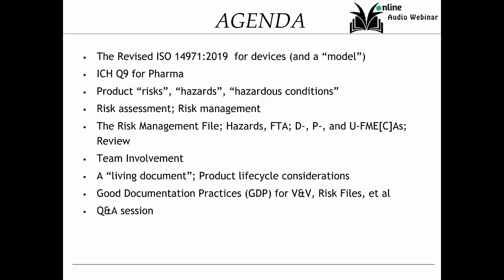You have your risk management file. It talks about the discussion of the issues, a list of hazards, and then you're given some choices of documents you want to use later, like HAZOP and others. I settled on fault tree analysis, and for design, process, and use, FMECA. In no case do I use FMEA or FMECA as failure mode effect criticality analysis alone. And then you have a review and report. You involve a team in this, and I like to have a clinician as part of that team, familiar with the procedure and the device on the patient. And then it's a living document under change control, updated as needed. And of course, good documentation practices are involved as well.